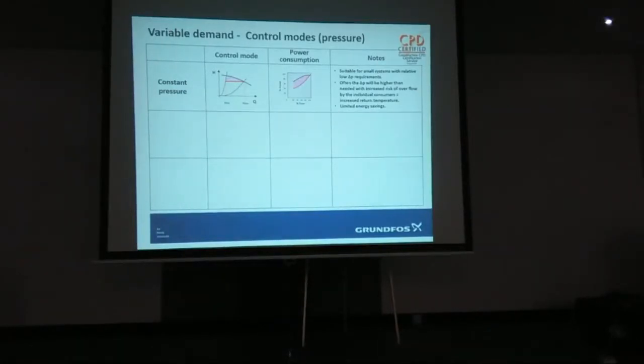Yeah, that's all right. It works to a degree. It doesn't give you that much in the way of energy saving. It gives you a little bit of control, but not a huge amount. You do save some energy when it slows down. It's okay where most of the resistance is in your control valves, not in the pipe, long runs of pipe. If you've got long runs of pipe, you don't use that method.